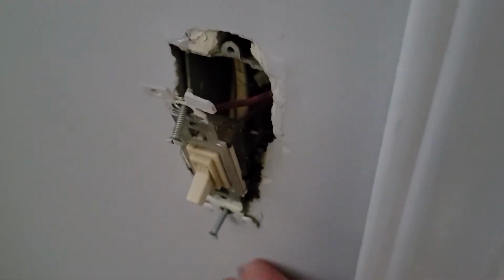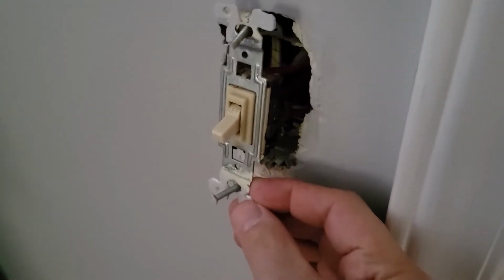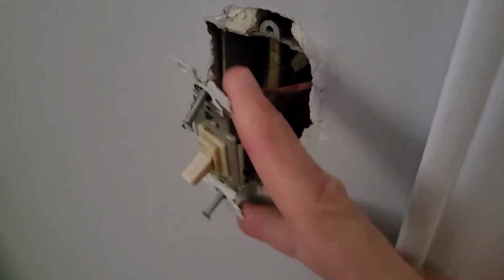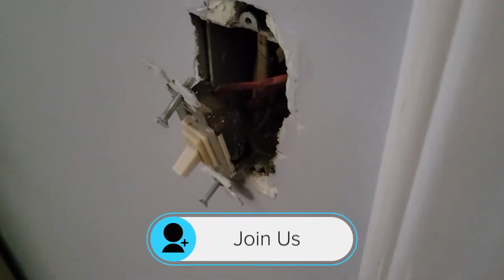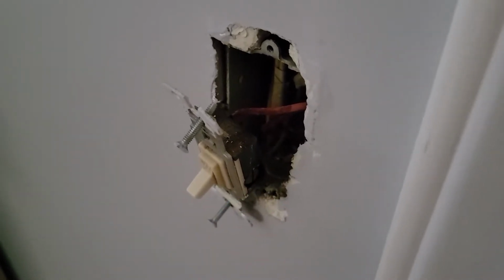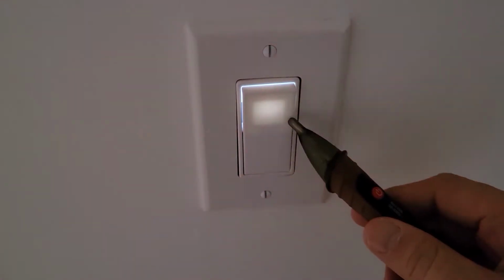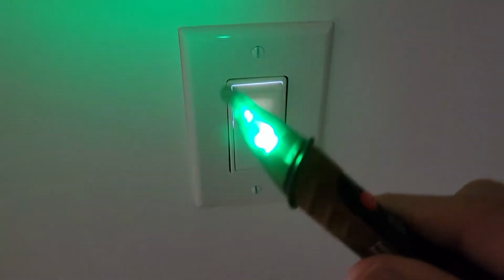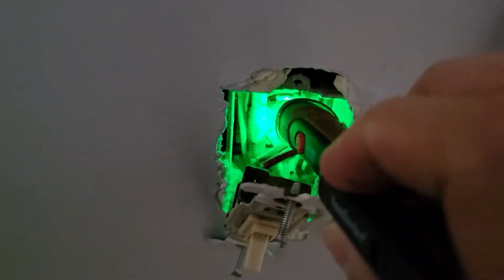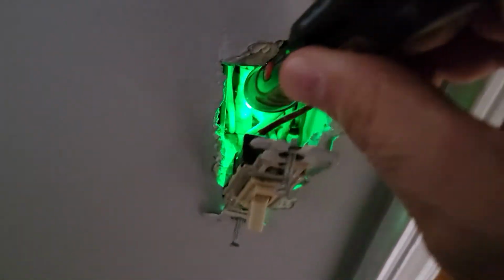Even though I know there's no power coming to the circuit, I don't know about any other wires that may be in this box. So I'm careful as to what I touch, and until I confirm with a test probe, I'm not going to touch the wires. I test my probe on a working device so it detects voltage, confirming it's working. Now I probe all the wires in the box to make sure there's no live current I need to be aware of. It looks like everything in the box is non-operative at this point, so we are safe to pull this out.